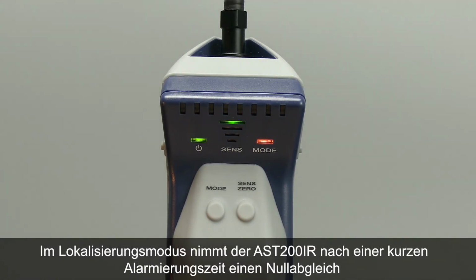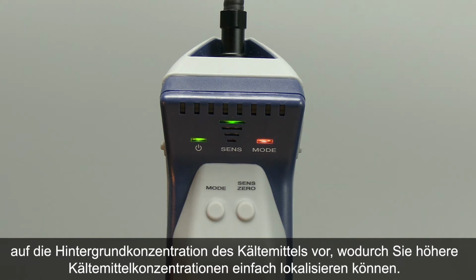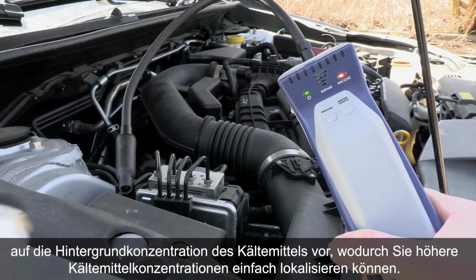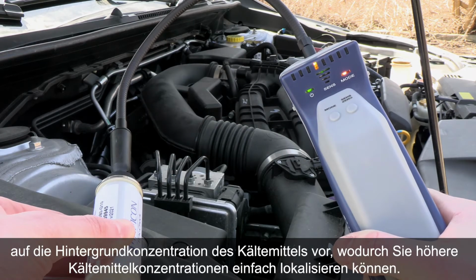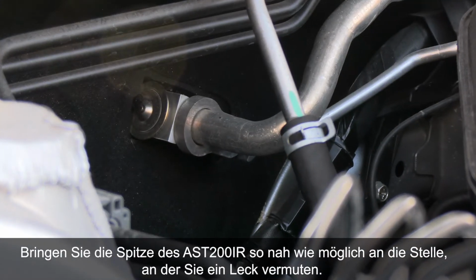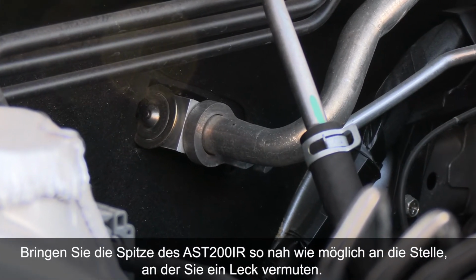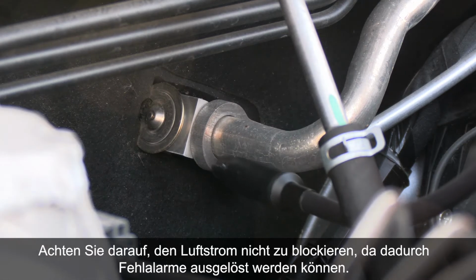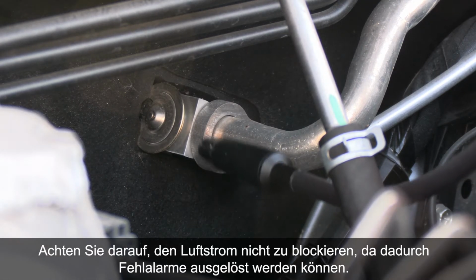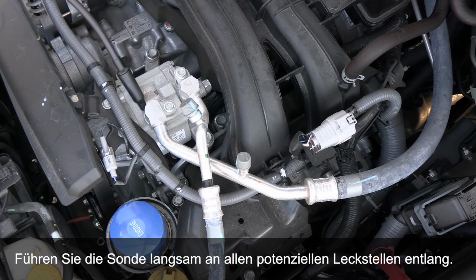In pinpoint mode, AST200IR will automatically zero to the refrigerant background after alarming for a short time, allowing you to easily locate higher levels of refrigerant. Place the tip of AST200IR as close as possible to the suspected leak. Be careful not to block the airflow, as this can cause false alarms. Slowly move the probe past each possible leak point.